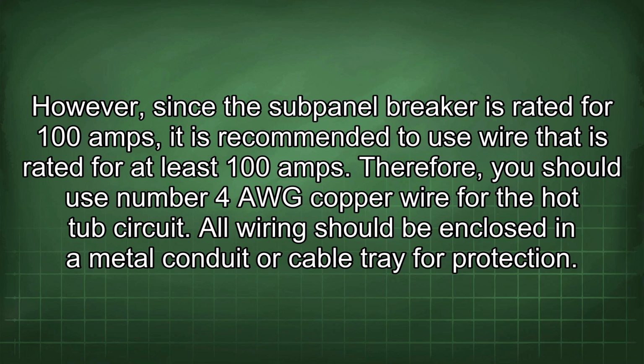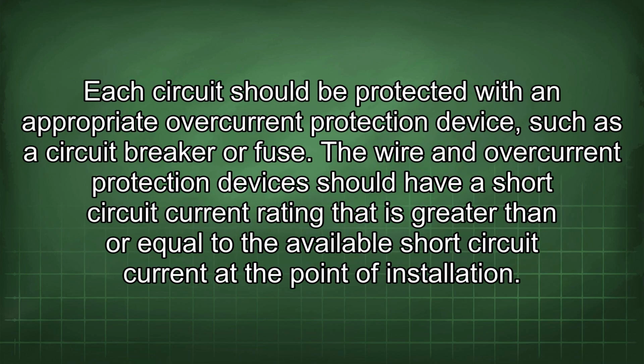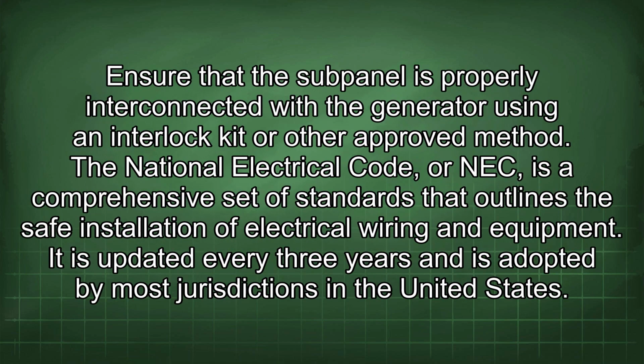All wiring should be enclosed in a metal conduit or cable tray for protection. Each circuit should be protected with an appropriate overcurrent protection device, such as a circuit breaker or fuse. The wire and overcurrent protection devices should have a short circuit current rating that is greater than or equal to the available short circuit current at the point of installation. Ensure that the subpanel is properly interconnected with the generator using an interlock kit or other approved method.